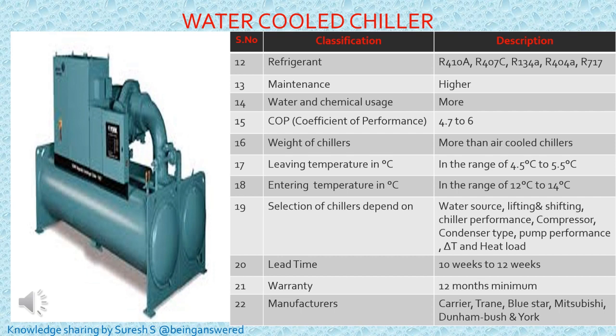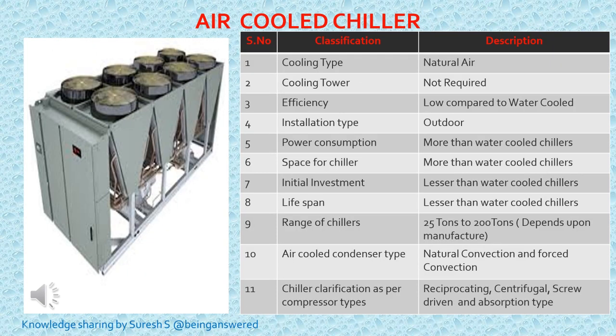Still more are there. I have given only a few names of the manufacturers. We will see the air cooled chiller. In an air cooled chiller, the cooling type is natural air. There is no external cooling mechanism provided for this type of chiller, so a cooling tower is not required. Efficiency will be low compared to water cooled, because the heat has to be dissipated through air. The installation type will always be outdoor, and the power consumption will be more than the water cooled chiller.